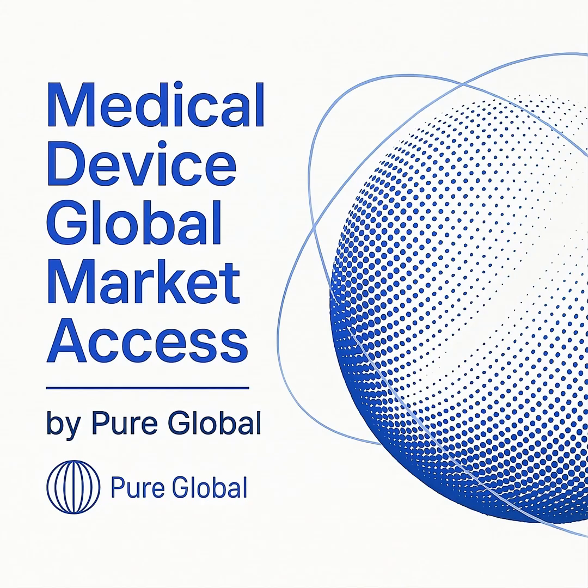For medical devices intended to be sold within the European Union, CE marking is mandatory. This mark signifies compliance with the EU Medical Device Regulation, often referred to as MDR, and its General Safety and Performance Requirements, or GSPR. The journey to obtaining CE marking involves several steps. First, manufacturers must determine their device's risk classification. Then, they need to compile a comprehensive technical file detailing the device's design, intended use, and supporting evidence of conformity.